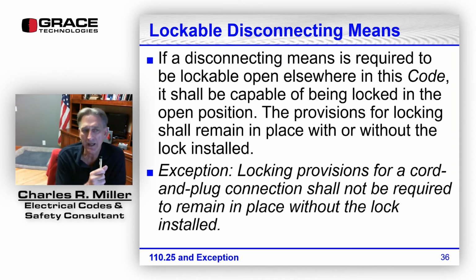It says, if a disconnecting means is required to be lockable open somewhere in the code, such as motors, it has to be capable of being locked in the open position. Here's a key part. The provision for locking shall remain in place with or without the lock installed. Let me go to the next slide.